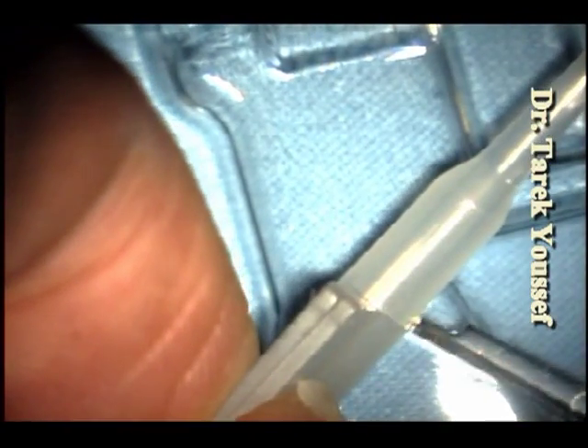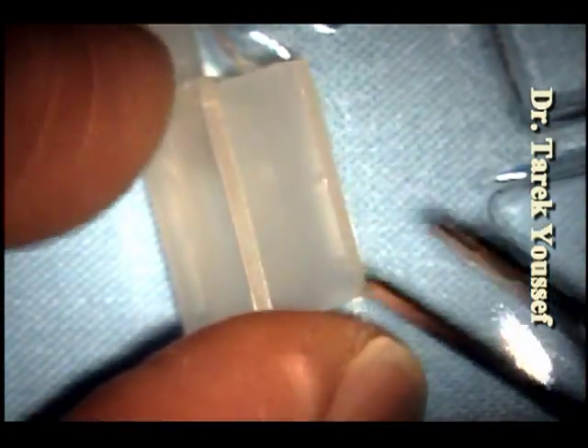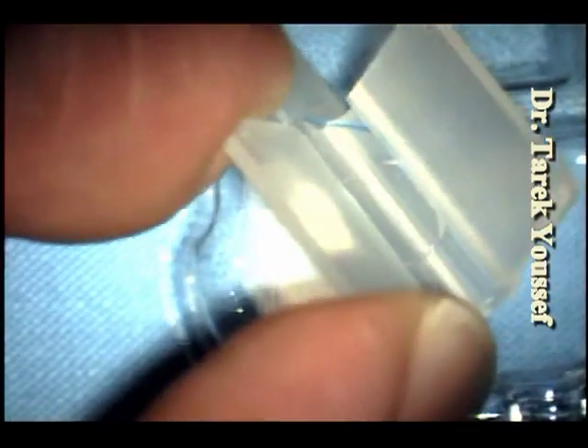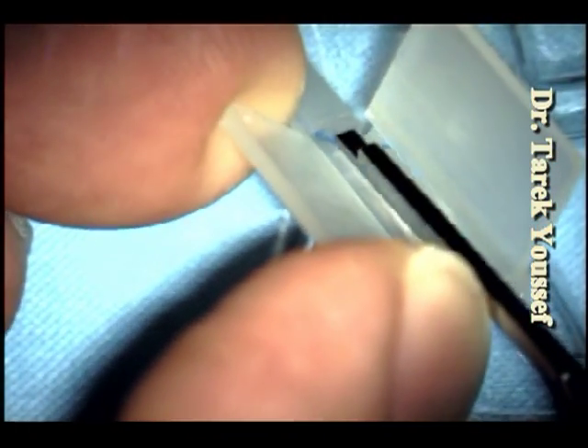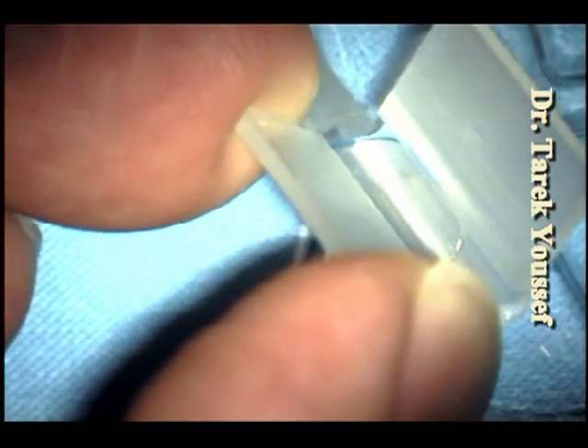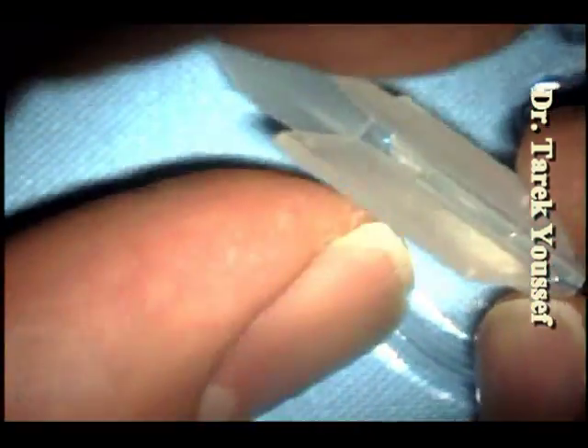The cases we did with this technique had no scratches on the lens. I think the problem is the design of the injector itself, because the injector should be able to do this process of closing down on the ridge and straightening it out. The injectors we have don't have that, and I'm working with the manufacturer to try to correct that. Thanks for watching.